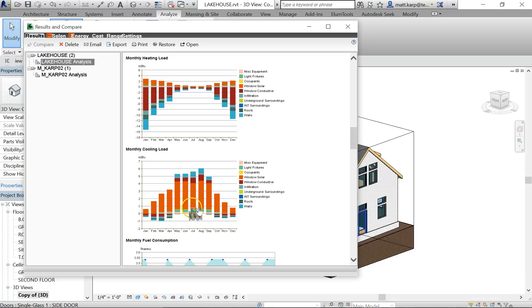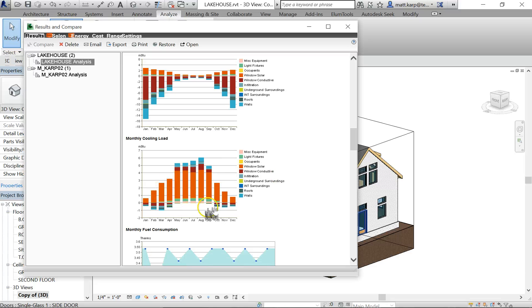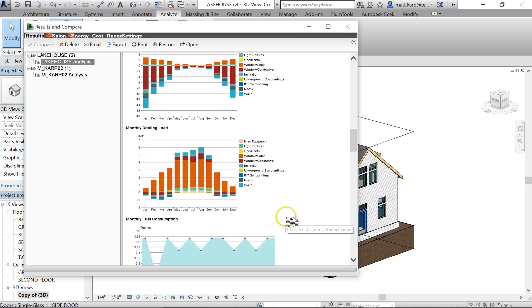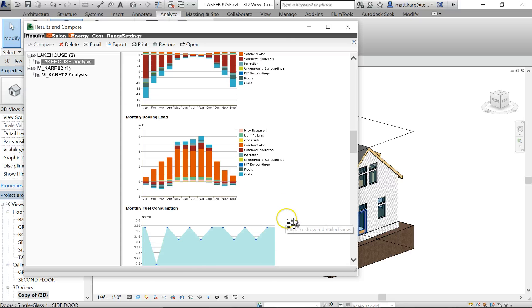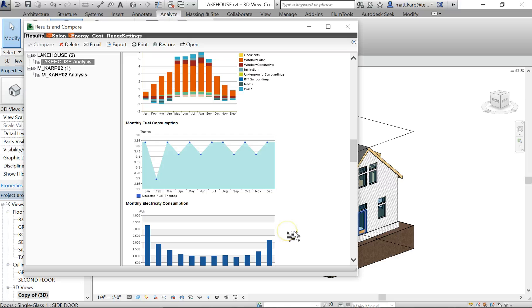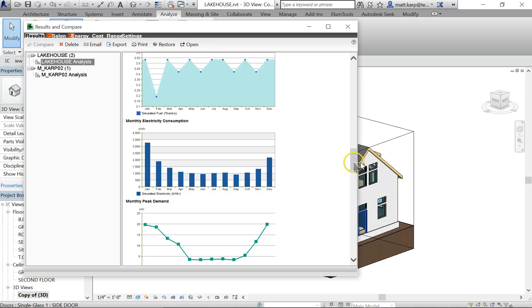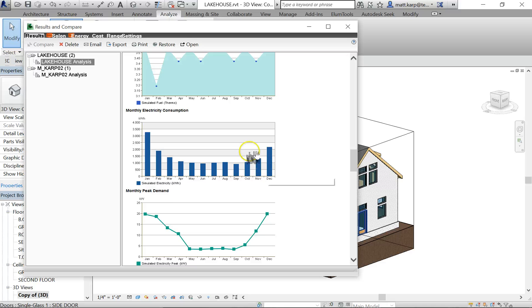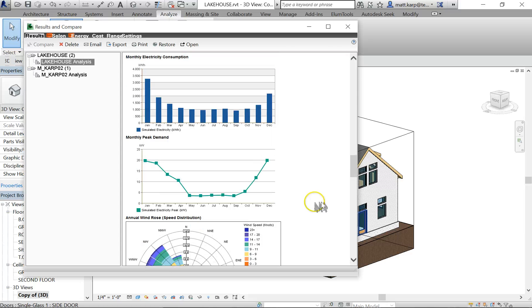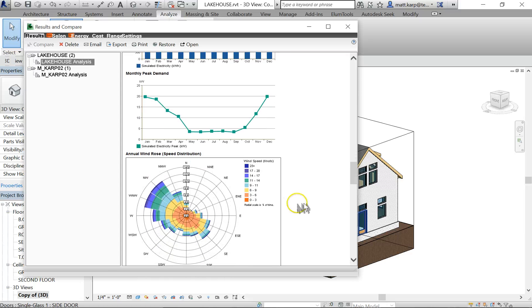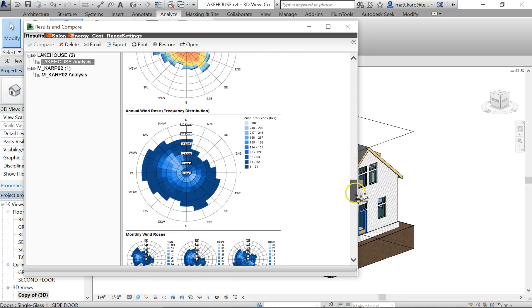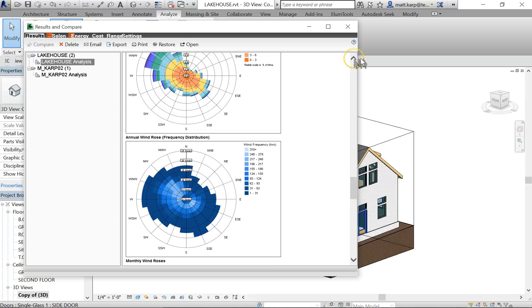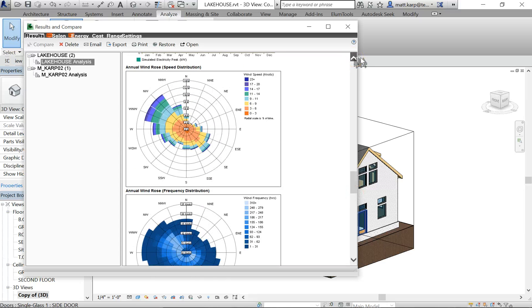And then it's the same thing in cooling. So cooling, we're gaining a lot of heat from our windows, so we're fighting to offset that. Fuel consumption - again with this HVAC we've selected, we're only using fuel for hot water, so that's going to be fairly consistent. Electricity just depends on the amount of cooling. Since it's an all-electric system, we do a lot more heating in this location than we do cooling it in the summer.